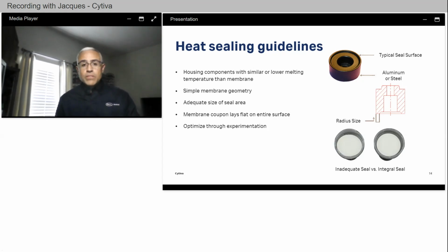temperatures than smaller devices. I'd like to point you to the image at the bottom right of the slide, which shows the difference between a partial seal and an integral one. A usual indicator of a good seal is transparency in the seal area, as you can see in the one to the right there. Also, the bond strength between the media and the housing surface can be evaluated by attempting to manually pull the media away from the sealing surface.